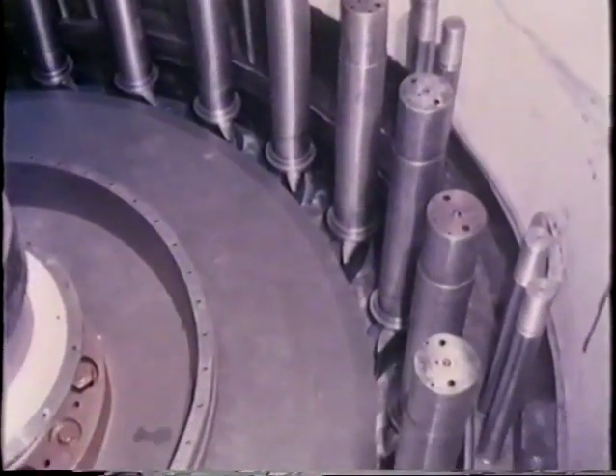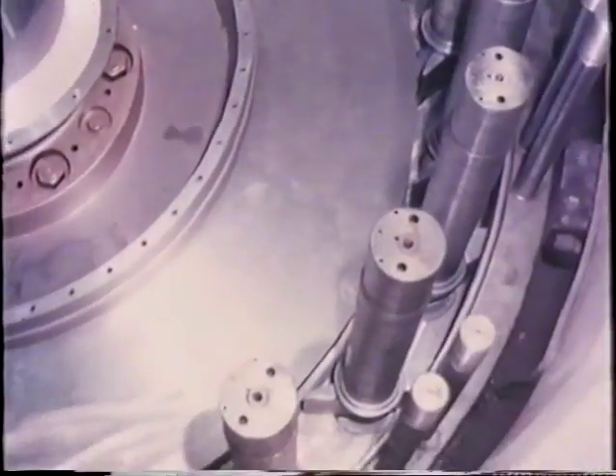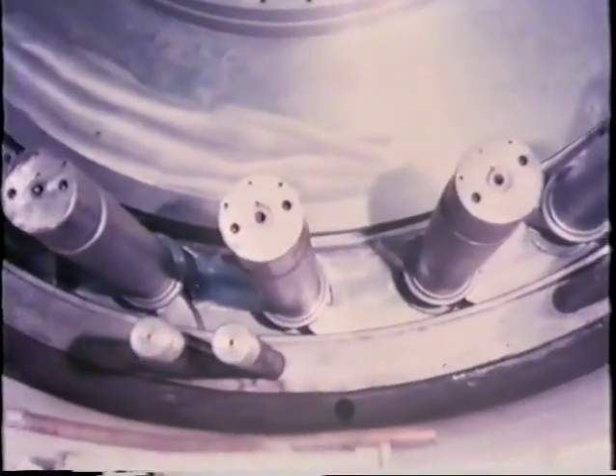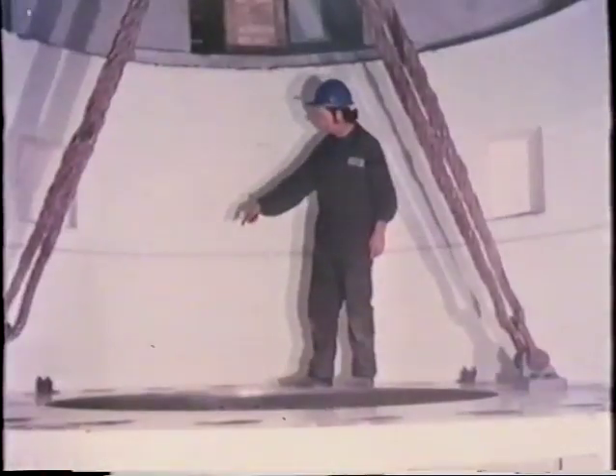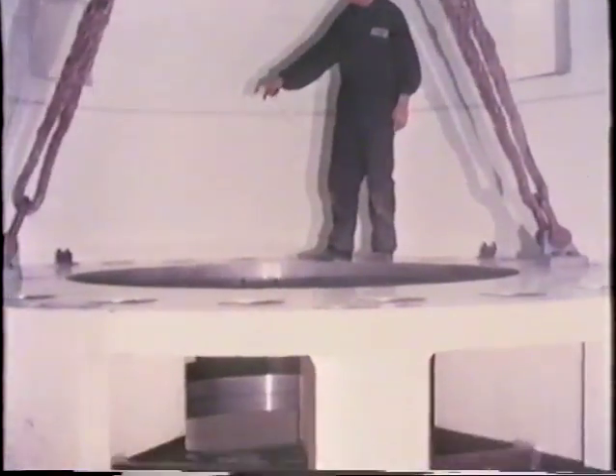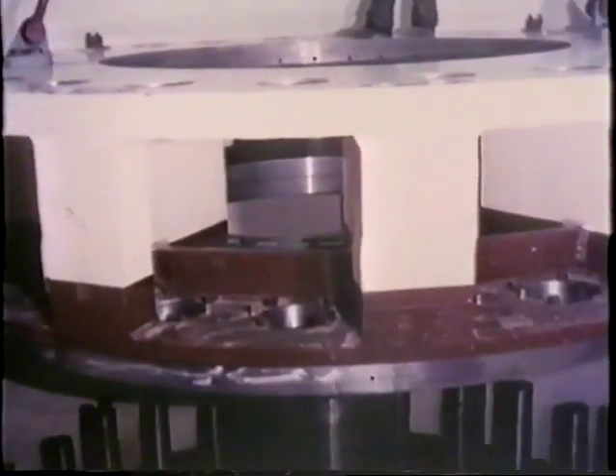Because of the load that can be applied to the head covers of reversible machines, special studies were made of their rigidity by model tests and finite element calculations. The resulting design is a prototype and has been most successful in operation. The object is to minimize leakages on the guide vanes by keeping the axial clearance small, while at the same time avoiding vane binding, which may occur if the covers deform under load.